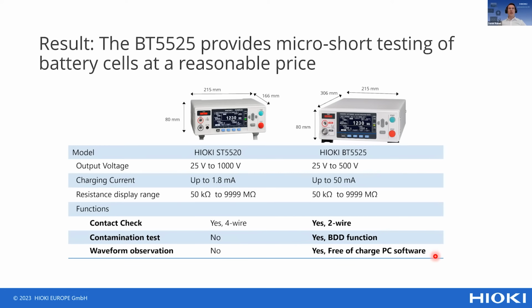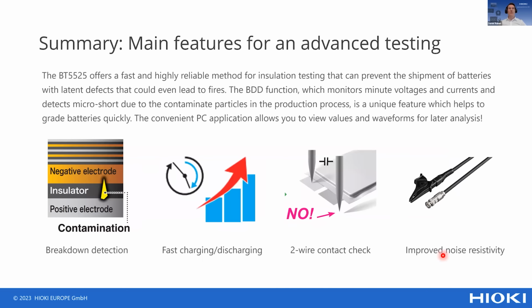Also, what is possible now, with the very fast sampling of the circuitry, is the chance to do a waveform observation. This gives you a better way to interpret how your battery cell is reacting and the reasons why it was happening. So as a summary, what brings the BT5525 to the market? The breakdown detection technology, which is completely new in the market, not only monitoring voltage, but current and voltage, so much more sensitive to detect any contamination inside the battery cell and if you have partial discharges.